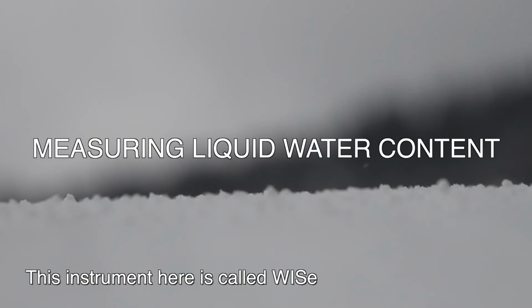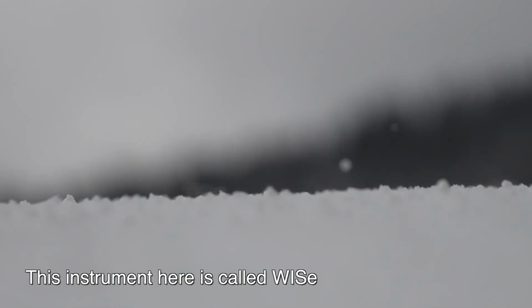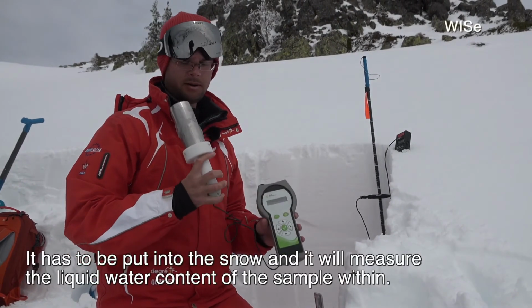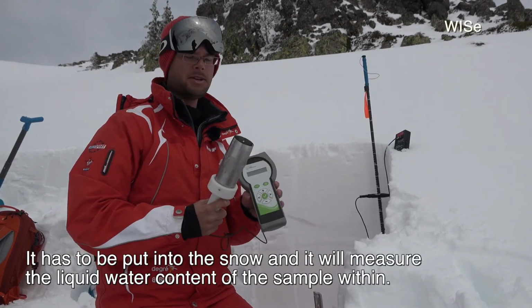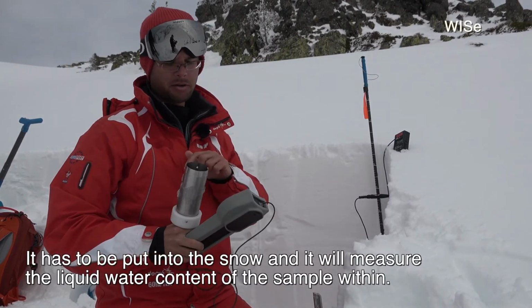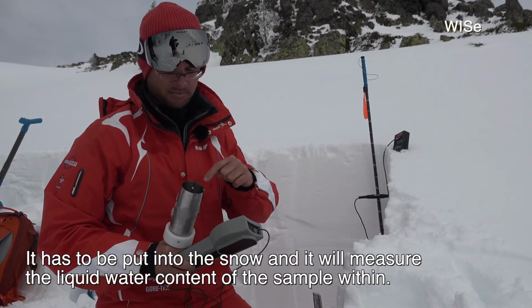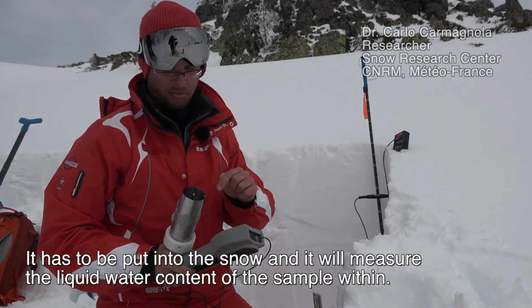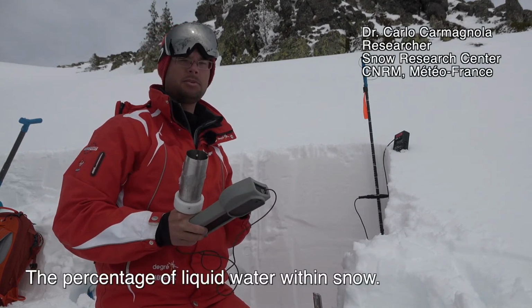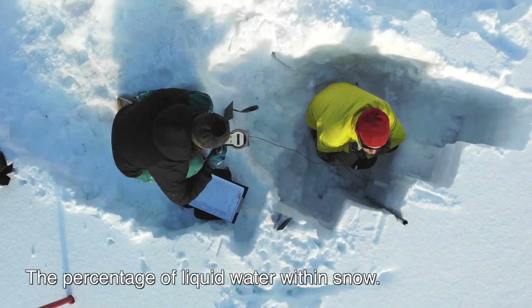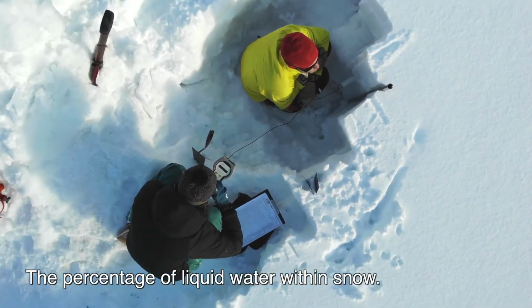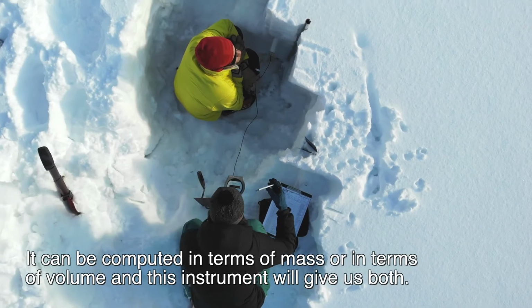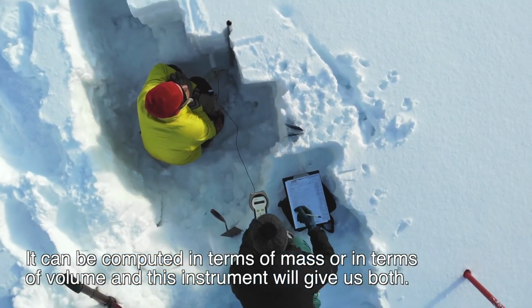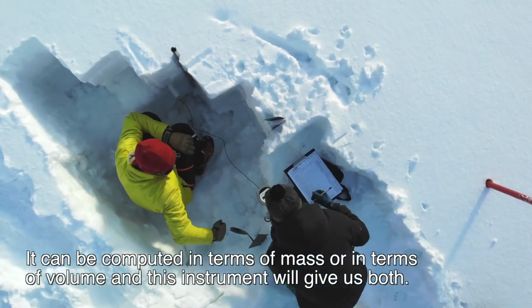So this instrument here is called WISE. So how does it work? Basically, it has to be put into the snow, and it will measure the liquid water content of this sample within. So it's the percentage of liquid water within snow. And it basically can be computed in terms of mass or in terms of volume, and this instrument will give us both.